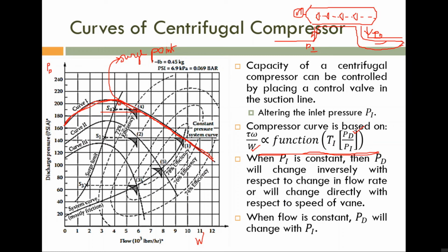The gas will flow back to the inlet side, means the vibration of the compressor will start. Why? The compressor is trying to push the gas to the discharge line, but the flow is reversed. So the energy or power given to the compressor is used to oppose that reverse force. So definitely vibration will start. It is known as the unstable region.